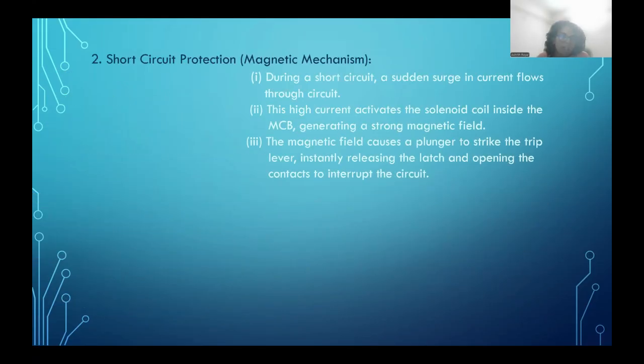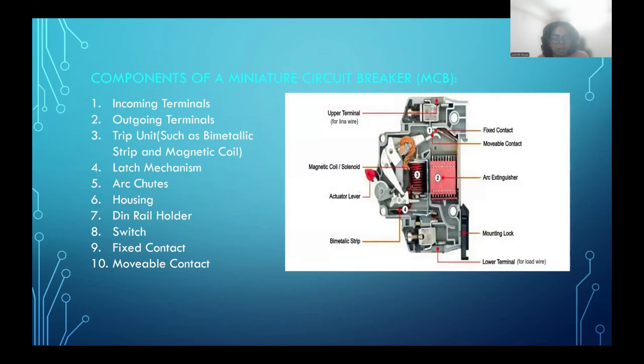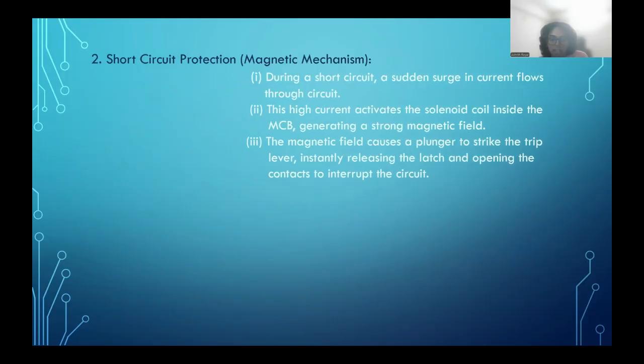Second is short circuit protection. During a short circuit, a sudden surge of current flows through the circuit. This high current activates the solenoid coil inside the miniature circuit breaker, generating a strong magnetic field. This magnetic field causes a plunger to strike the trip lever instantly, releasing the latch and opening the contacts, which also opens the circuit. Third is arc extinguishing. When the contacts open, an electrical arc is formed between them.